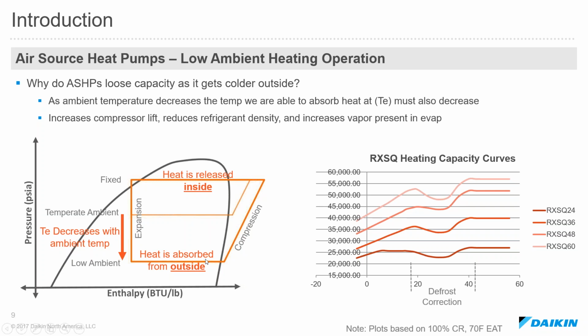And then also the distance between these two horizontal lines. The more that increases, the more energy it takes, the more work the compressor has to do to bring that pressure up from the low ambient conditions up to the constant temperature that we like to see on the indoor side. And this all results in what you see on the right-hand side there, a capacity curve that starts to drop off as it gets colder outside.